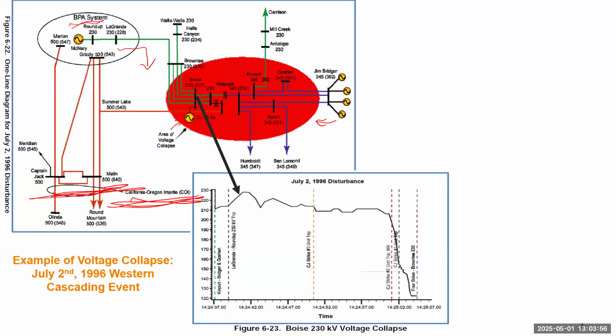if you measure how the voltage changed along that transmission corridor, you mainly focus on the Boise substation. You can measure the voltage magnitude. That substation is a 230 kV substation, so voltage should be around 230 kV. Here is the normal voltage, 230. After some event the voltage changes, and eventually the voltage declined very quickly. It became out of control. So let's see what happened.